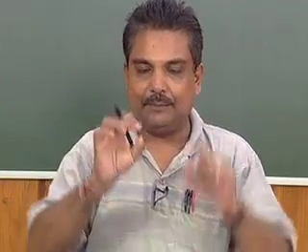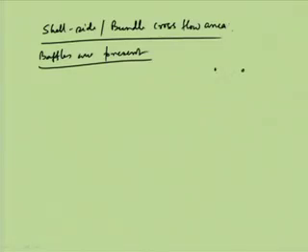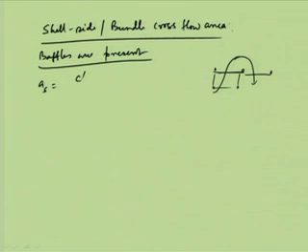So, if this is the distance between two baffles, the fluid will pass like this and then come like this, through another distance between two baffles. This is the cross flow area that we have to calculate. It is given by AS equals C dash into B into DI by PT, where C dash is the clearance between tubes, B is the baffle spacing, DI is the inner diameter of the shell, and PT is the tube pitch.